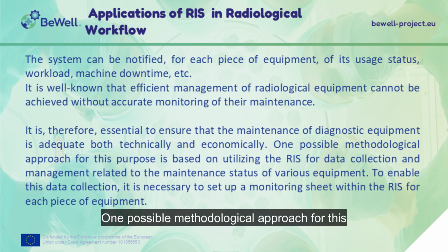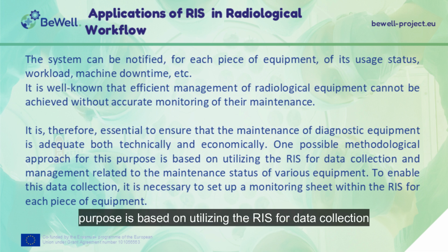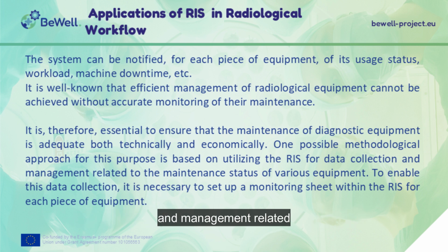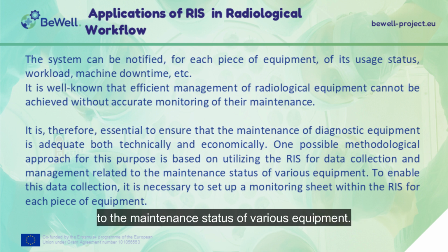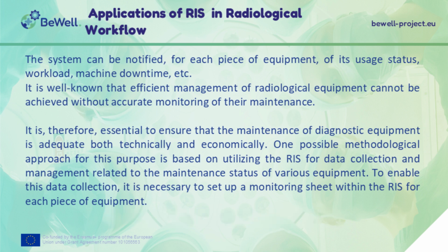One possible methodological approach for this purpose is based on utilizing the RIS for data collection and management related to the maintenance status of various equipment. To enable this data collection, it is necessary to set up a monitoring sheet within the RIS for each piece of equipment.